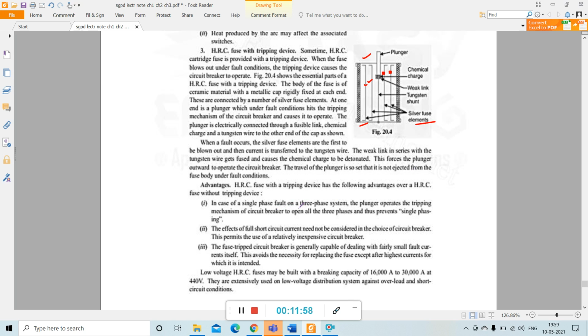In case of a single phase fault on a 3-phase system, the plunger operates the tripping mechanism of the circuit breaker to open all 3 phases, which prevents single phasing. The effect of full short circuit current need not be considered in the choice of circuit breaker, because this permits the use of a relatively inexpensive circuit breaker. When we use a circuit breaker with these fuses, the fuse reduces some of the fault current, so that we can use low rated circuit breakers. The circuit breaker need not handle the full amount of short circuit current, because some part of it is handled by the fuse.